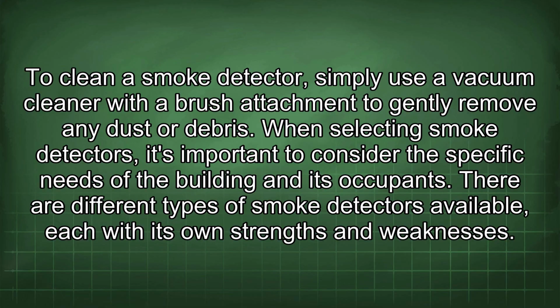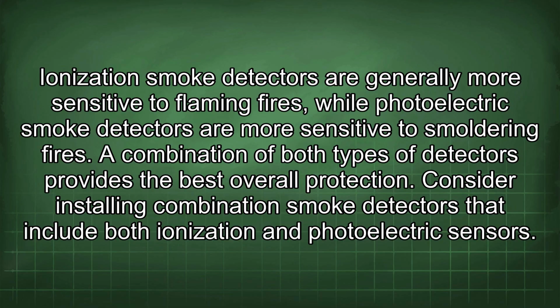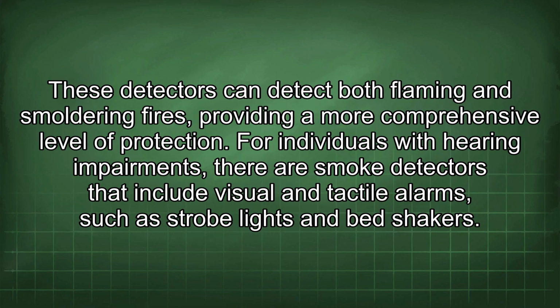When selecting smoke detectors, it's important to consider the specific needs of the building and its occupants. There are different types of smoke detectors available, each with its own strengths and weaknesses. Ionization smoke detectors are generally more sensitive to flaming fires, while photoelectric smoke detectors are more sensitive to smoldering fires. A combination of both types of detectors provides the best overall protection. Consider installing combination smoke detectors that include both ionization and photoelectric sensors. These detectors can detect both flaming and smoldering fires, providing a more comprehensive level of protection.